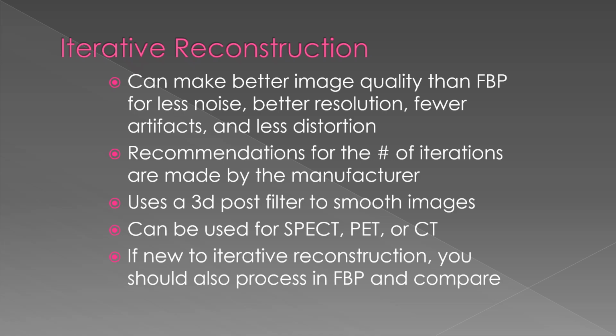And you can make better image quality with iterative reconstruction than filtered back projection for less noise, better resolution, fewer artifacts, and less distortion. Recommendations for the number of iterations are made by the manufacturer. These are usually built into the protocols. You do have the ability to go in and change it, but these are manufacturer recommendations.